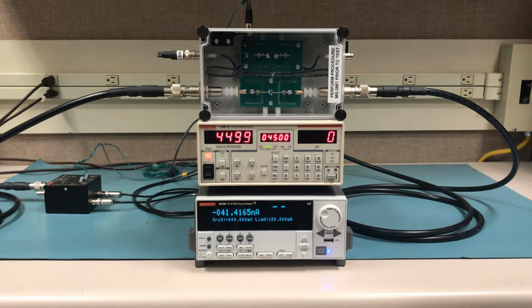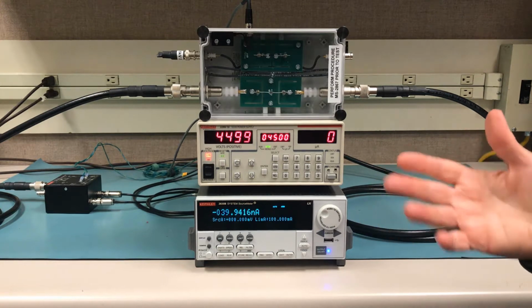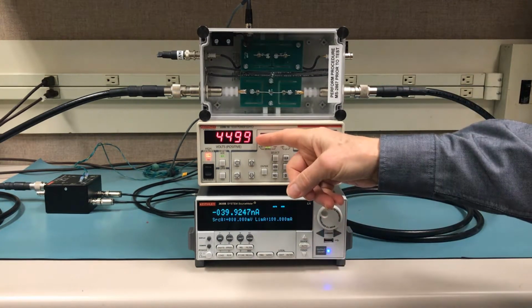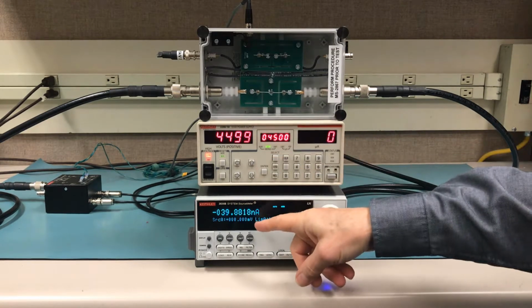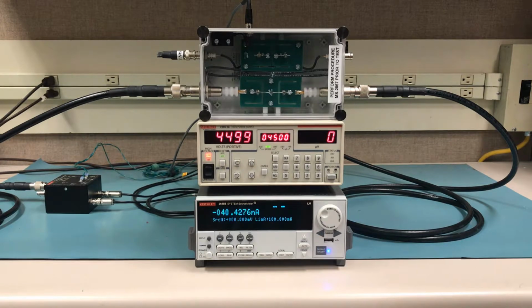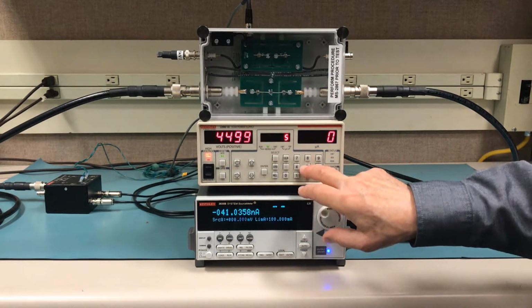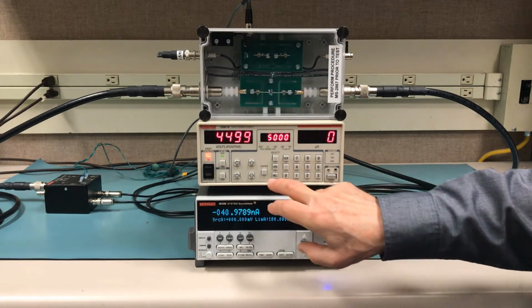And our current is still in the nanoamp range, so we're still very much along the horizontal part of the reverse voltage diode curve. If we were interested in measuring the resistance, in case this was a resistive element, we can just divide the voltage, 4,500, by the measured current to get the resistance. So let's be aggressive. We'll go to 5,000 volts.